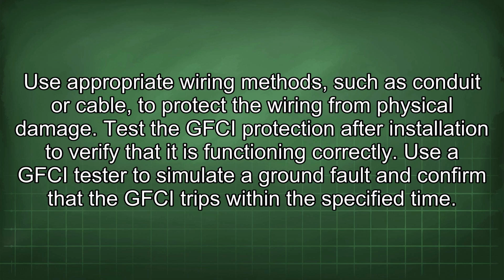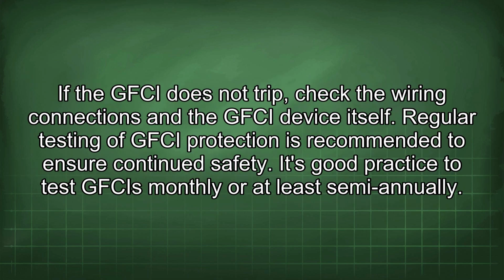Test the GFCI protection after installation to verify that it is functioning correctly. Use a GFCI tester to simulate the ground fault and confirm that the GFCI trips within the specified time. If the GFCI does not trip, check the wiring connections and the GFCI device itself. Regular testing of GFCI protection is recommended to ensure continued safety. It's good practice to test GFCIs monthly or at least semi-annually.